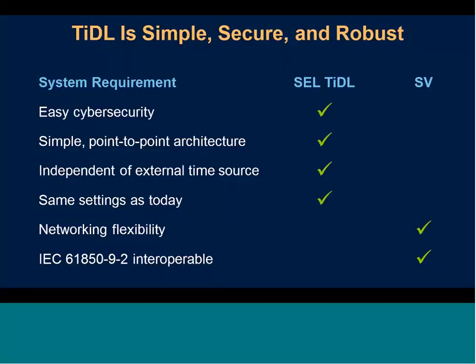That's not to say that sampled values does not have some advantages. The flexibility in networking is a big one. I showed that one example, and while it does take extra complexity to engineer failover paths, it does help mitigate some concerns about points of failure, since it can have redundant switches, redundant clocks, and all of that. With the trade-off being I have to engineer those paths, account for all of this data, and make sure I'm being responsible in where my data is going and how it's being delivered.